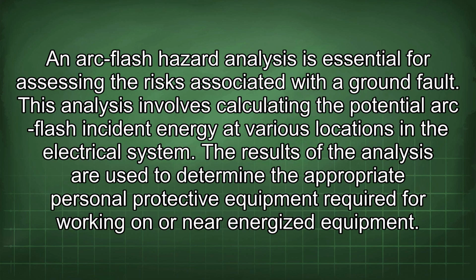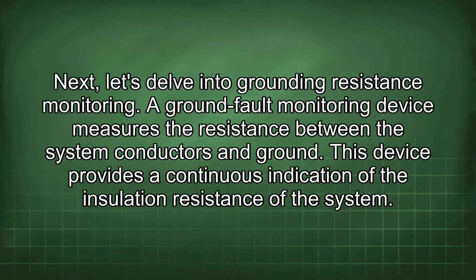An arc flash hazard analysis is essential for assessing the risks associated with a ground fault. This analysis involves calculating the potential arc flash incident energy at various locations in the electrical system. The results of the analysis are used to determine the appropriate personal protective equipment required for working on or near energized equipment. Next, let's delve into grounding resistance monitoring.